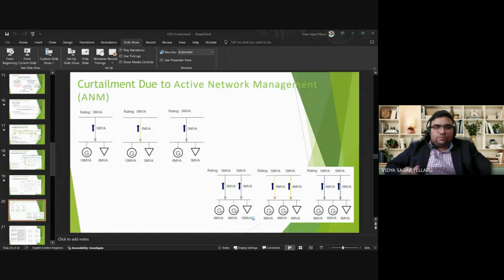Here, this is the asset. This is the line having a rating of 5 MVA, and there is a generator of 10 MVA and a local demand of 8 MVA. The generator has to supply power to this load, and after that there is an excess power of 2 MVA that can pass through this particular asset of rating 5 MVA. Then this is the most ideal case. Nothing is overloaded here and this passes.